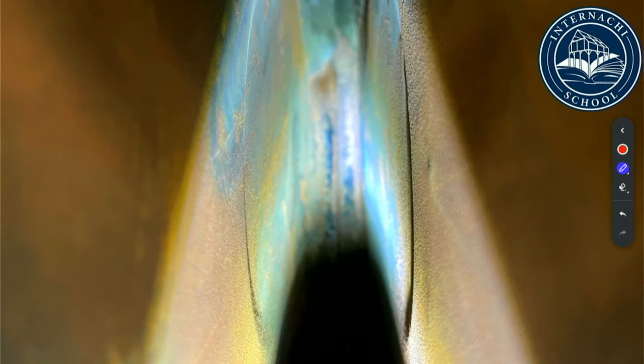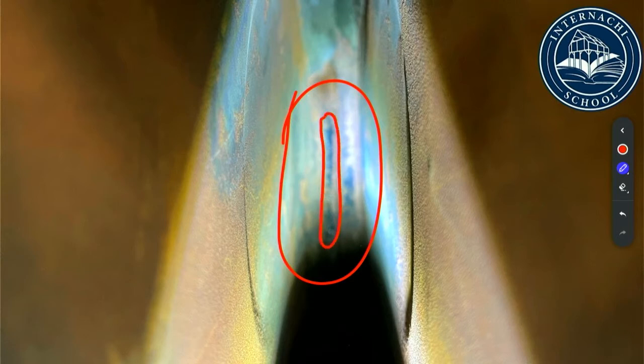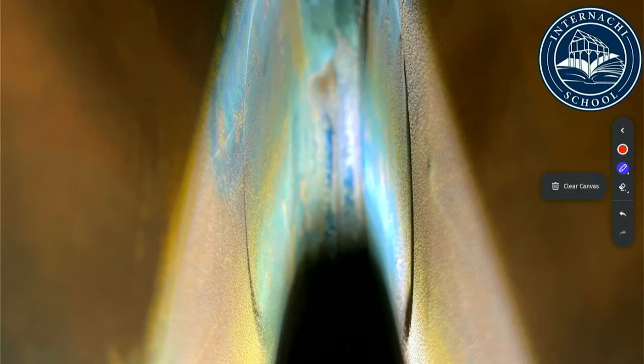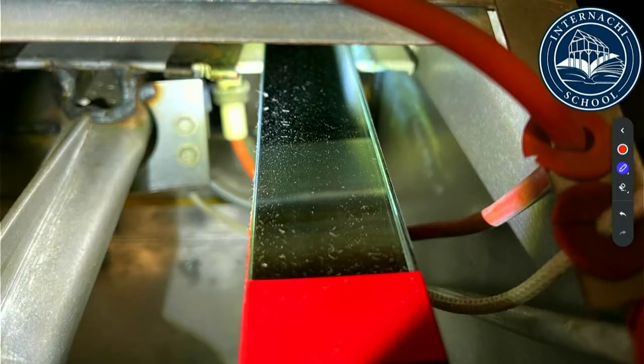Usually you're going to find holes and cracks in these heat exchangers in the back. Very difficult to take a picture of it, but that's what we're looking at there in the back. The other common place is right up underneath where it enters. If you go inside the hole and peek right up in there, that's typically the other popular place. This is what the mirror looks like when you go inside there.